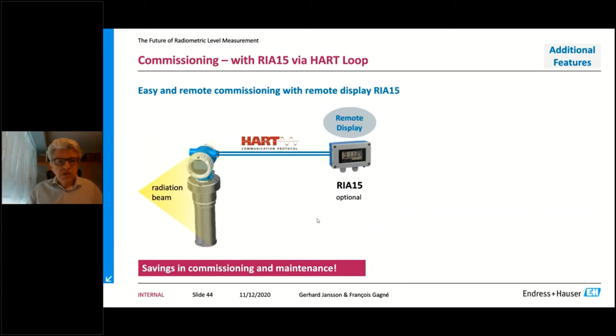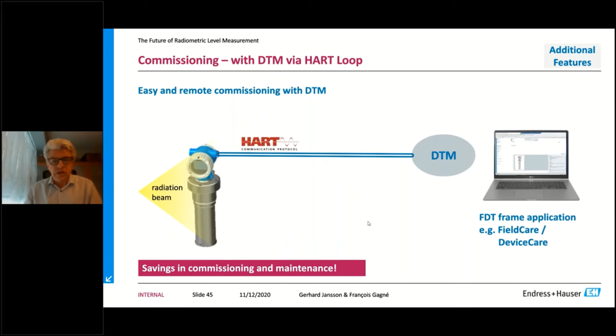Of course, you also have the option of a display that you can configure from. There is a display on the instrument itself, but it's just for visualization, not for configuration, because we don't want anyone to stand here for a longer time to configure an instrument, since we don't know how much radiation there is. We do sizing, but sizing is as good as the information we've received. So this is one alternative, and of course doing it with software, where you have a laptop and connect over a HART modem to the instrument, is also an alternative way of doing it. All three options are available.